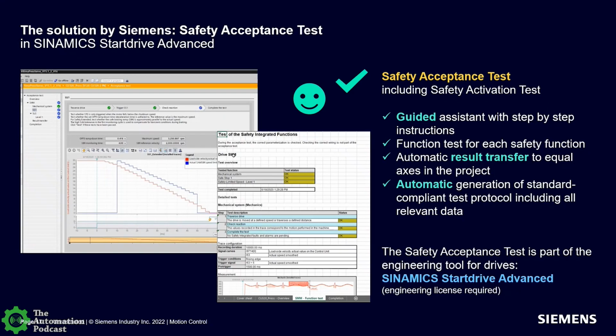But where we've made some additional innovation as well is the safety acceptance testing. So once it's up and running, and you are going to do the last part of your risk analysis, which is the verification and documentation, we're able to support that as well with our software tools. So with Startdrive Advanced, we can go in and do a safety acceptance test. That safety acceptance test is where we go into each drive axis, and we test the safety functions that are enabled. So it's going to allow us to test them and document them and say, okay, when it was finalized in its commissioning, we document this is the parameter set.